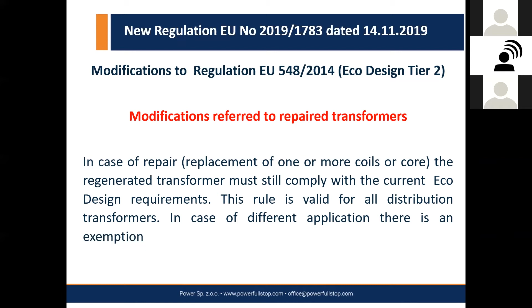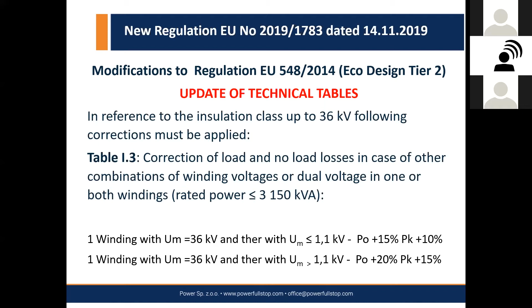There was a short update also referred to the technical tables. I've just listed a few of them. It's referred to class 36 kV, which is quite a high class for medium voltage - the higher step for medium voltage transformers. So the losses have been defined and described very clearly in this new regulation, referring to a combination of winding voltages, or dual voltage in one or more windings. As you can see, the losses are defined here by plus 15 for PO, and plus 10 for PK, changing a little bit depending on which voltage we're dealing with. I will not list them all.